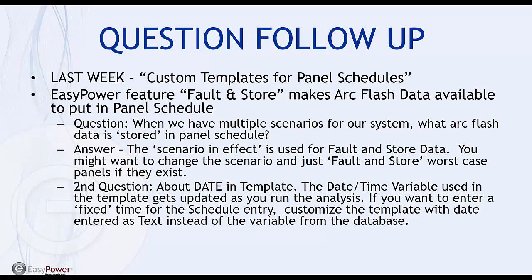Last week's refresher, we did a session on custom templates for panel schedules. A couple questions came up regarding utilizing the arc flash analysis results in the template. Specifically, Fault and Store allows us to put the arc flash data in the panel schedule. So the question is, if you have multiple scenarios for the system, what data is stored? And the answer is whatever scenario is in effect at the time will be loaded into the panels that are part of the study.